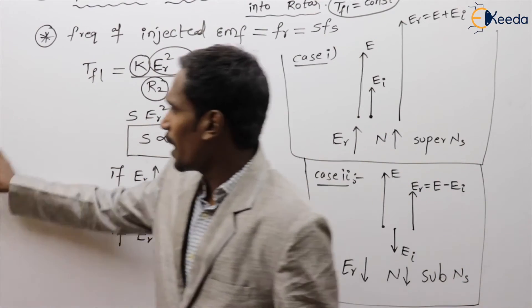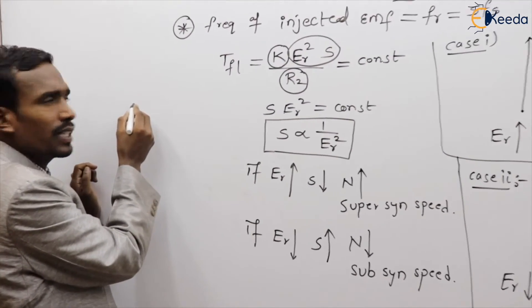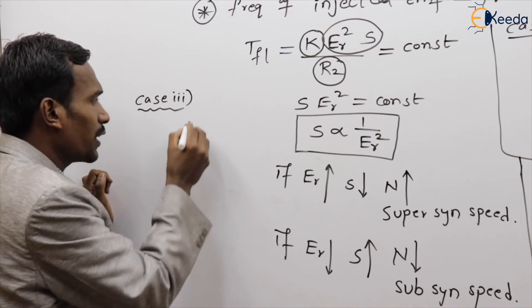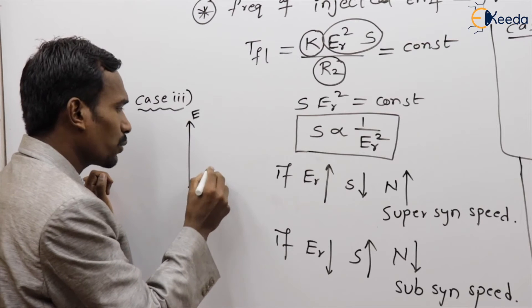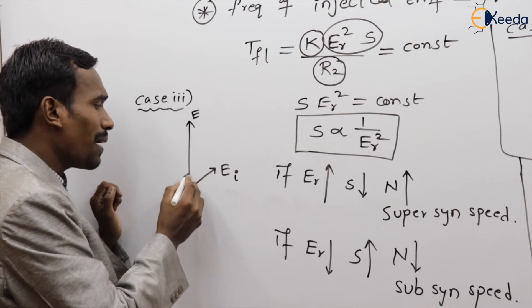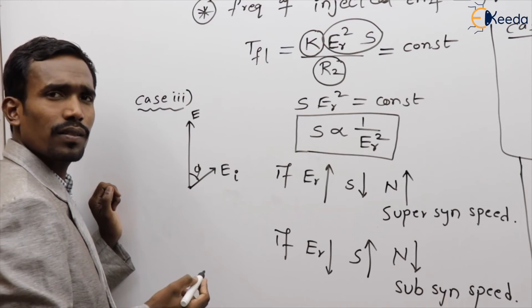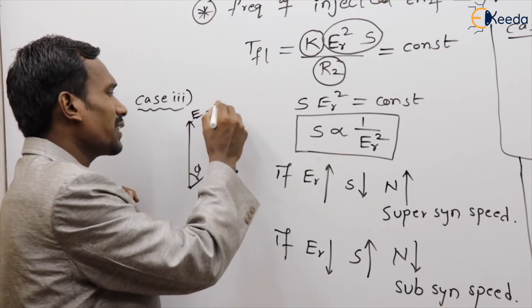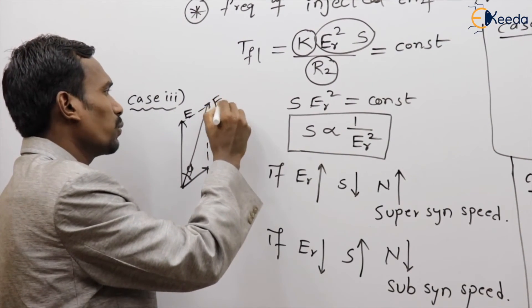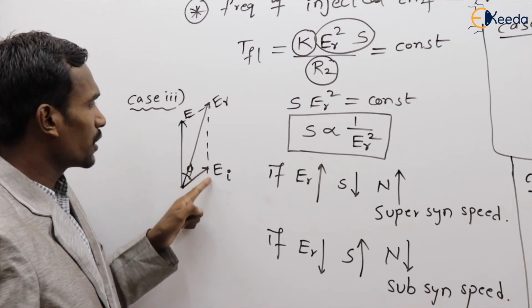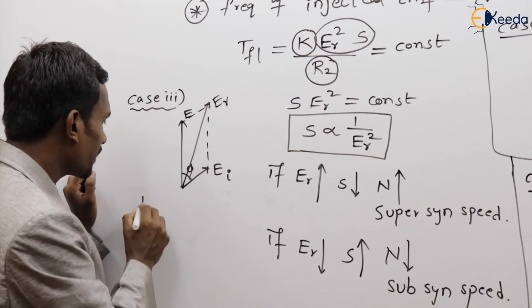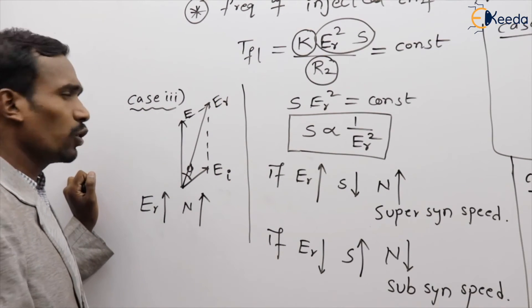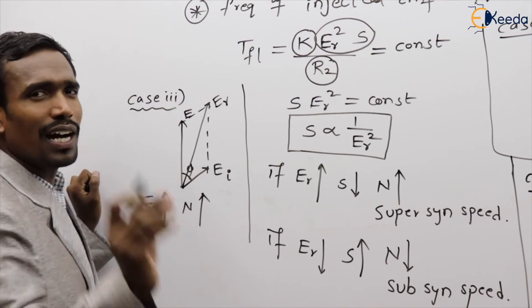Case three: the EMF is injected into the rotor with some angle — not exactly in phase but at an angle phi. The resultant ER is the vector sum of the actual rotor EMF and the injected EMF. In this case ER increases, so speed increases — super-synchronous speed. Importantly, when EMF is injected with some angle, we can also control the power factor.